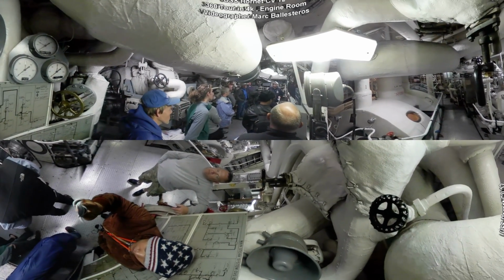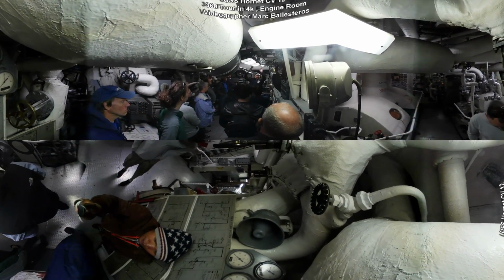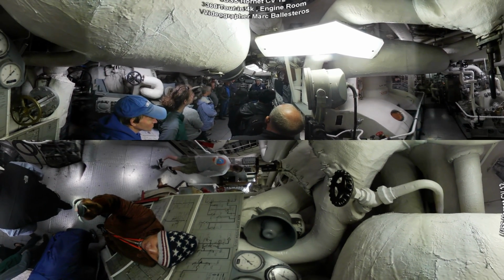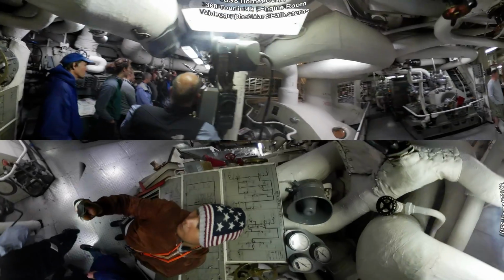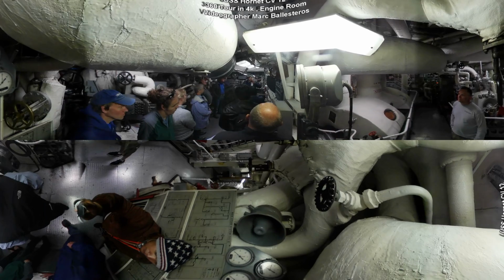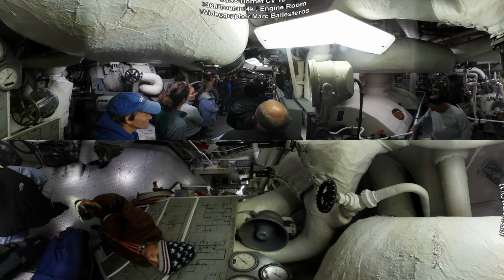If you come over here, for example, and they say slow down or stop, and you have an inexperienced throttleman and they do this, that steam has nowhere to go. The safety relief valve starts blowing open on top of that boiler. They shut the boiler down. This whole area goes dark. It'd be the responsibility of this poor person. Similarly, if they call down here and they say go fast, and this person doesn't think about it, what's going to happen is your steam pressure is going to drop. At 590 pounds, you lose your generator. Once again, everything goes dark. It's all on the shoulders of this poor 18-year-old that's right here. They could shut down this part of the ship. So hopefully they have enough training to be able to not do that, and enough supervision.